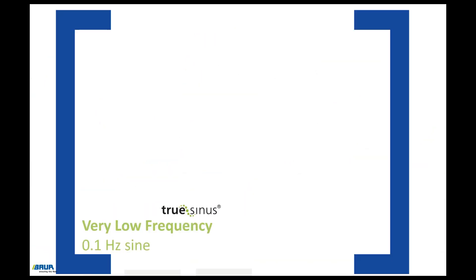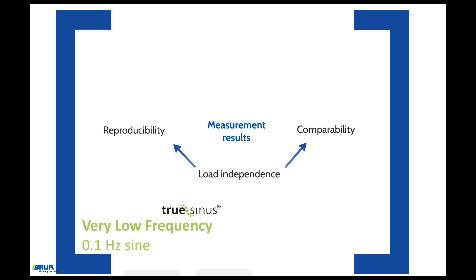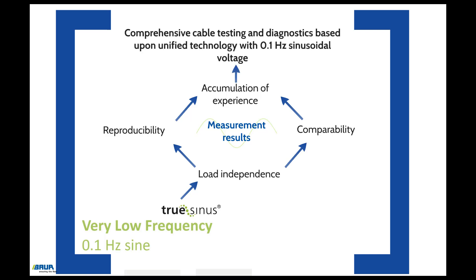Despite the advantages and disadvantages of each of the different testing and diagnostic methods — such as 50 Hz sinusoidal, 0.1 Hz sinusoidal, DAC, and 0.1 Hz cosine square wave — the 0.1 Hz voltage shape has the decisive advantage of reproducible and comparable measurement results. This is due to its load independence, which can only be achieved by the true sinusoidal 0.1 Hz voltage. Thanks to the comparability of the measurement results, the operator can build up empirical and reference values in the field of dissipation factor measurement and partial discharge testing. This comparability massively increases the benefits of cable diagnostics. A further advantage is that the sinusoidal 0.1 Hz technology can be used for all meaningful measurement methods, such as dissipation factor measurement and partial discharge testing.